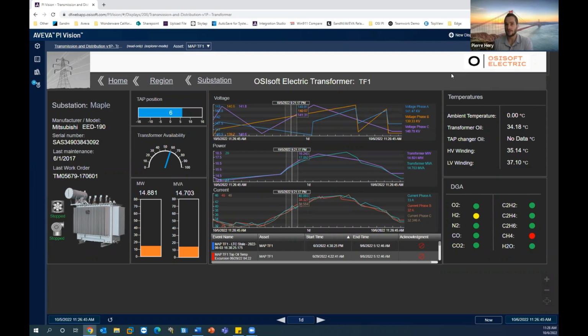Pi is more expensive than the Aveva Historian, and like I said, it's more appropriate for a tier 2 enterprise network, because at the end of the day, the Aveva Historian and the client tools for the Aveva Historian are more tailored toward technical folks like operators and engineers that work on the SCADA network, while Pi, as you can see here, is tailored more for non-technical folk that are on the enterprise network, right? So these are your decision makers that aren't necessarily operators or engineers, right? So you can use Pi on your SCADA network, but it's typically overkill.